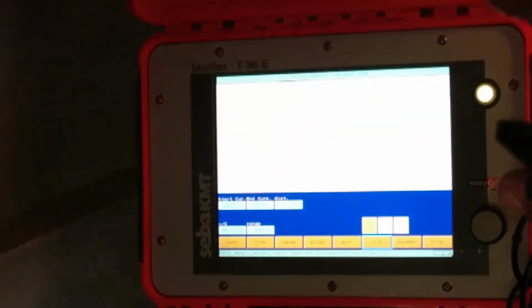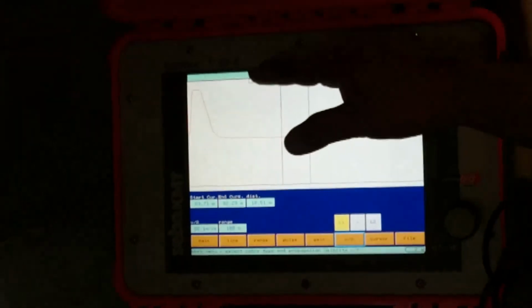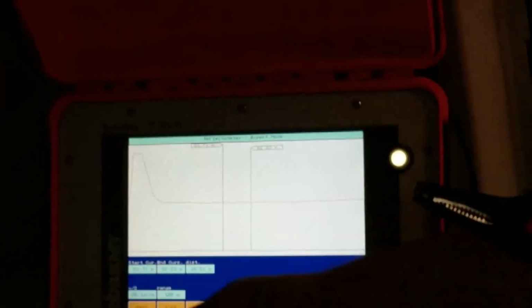You will never have all cores shorted. So you pick two - one faulty phase and one healthy phase - and you do an ohm test and compare these two traces together, looking for where the impedance changes on the cable. All cores should be the same, but if you compare two traces together like we did, you will see some difference in the impedance. I won't say 100% this is the fault, but there will be some change in the resistance. You can find this by TDR, or by doing an ohm test and comparing the two differences.